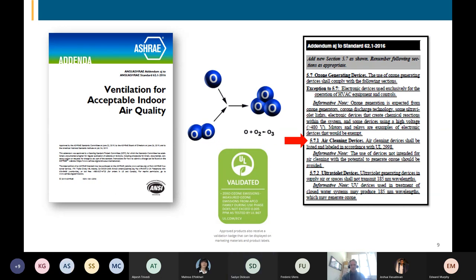Thank you. Okay, sure. Now, what's very important to understand about any of the categories of electronic air cleaning technology that I've talked about so far is that with regards to ASHRAE standard 62.1, ventilation for acceptable indoor air quality, section 5.7.1, it is important to make sure that that air cleaning device, and that is anything electric or electronic, I'll say it again, anything electric or electronic, including UVC lights, including needlepoint and bipolar ionization, including photocatalytic oxidation, dry hydrogen peroxide, electronic air cleaners, polarized air cleaning media filtration, whatever the case might be, shall be listed and labeled in accordance with Underwriters Laboratory Standard 2998 and validated for zero ozone emissions.